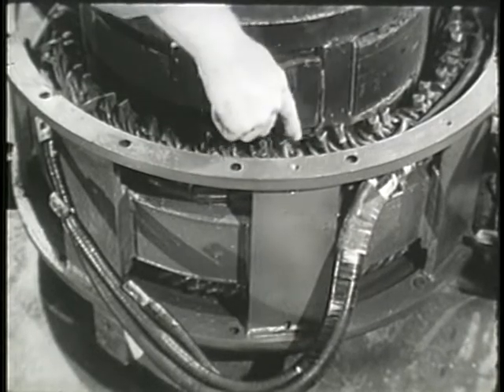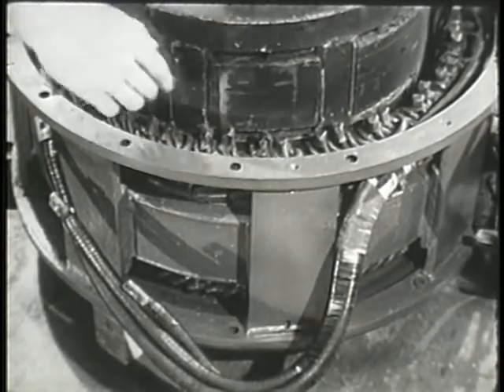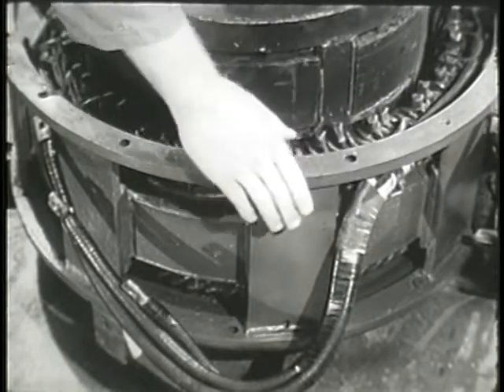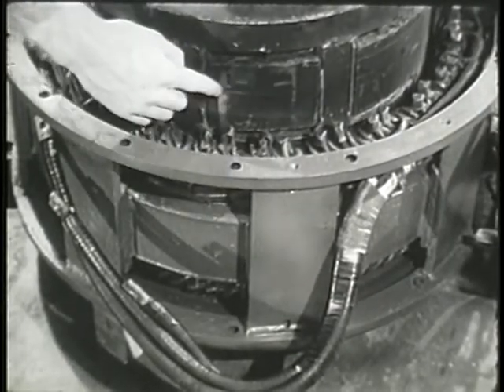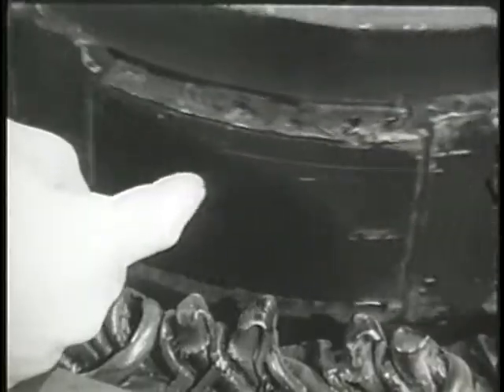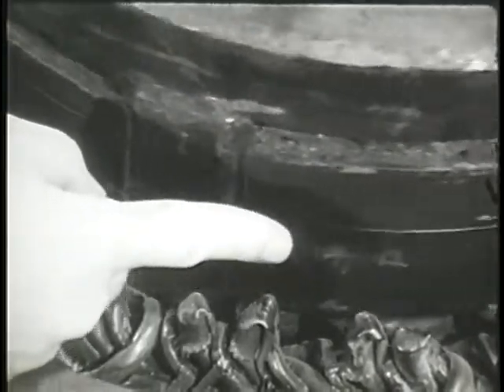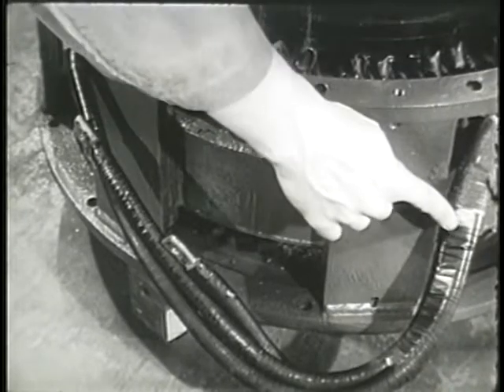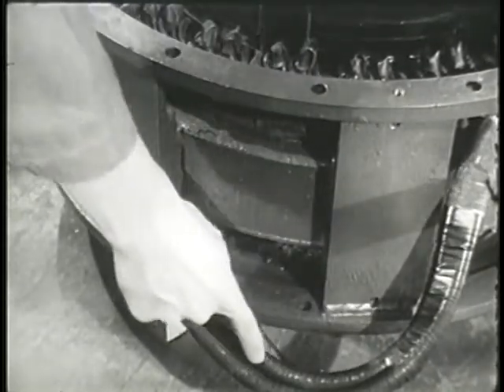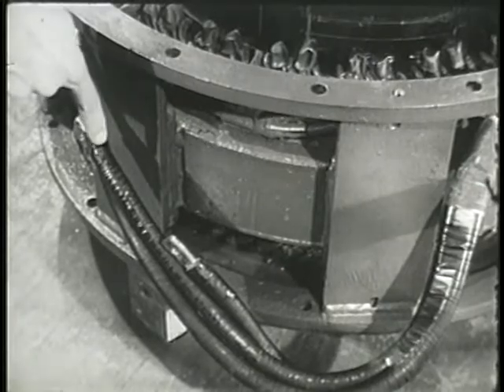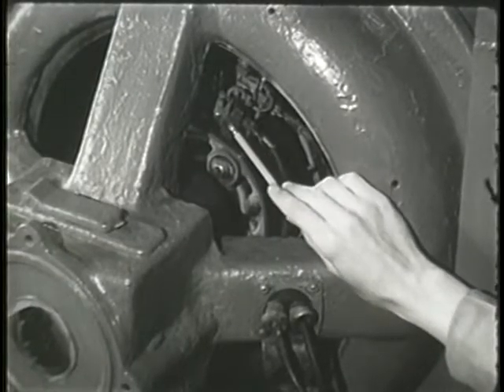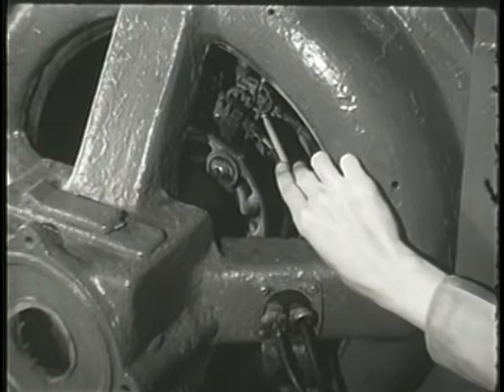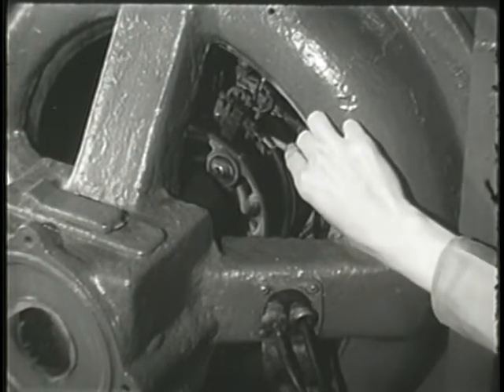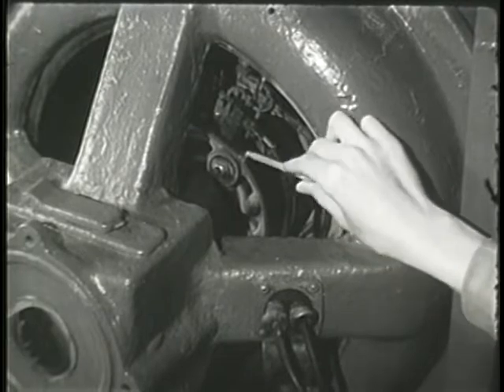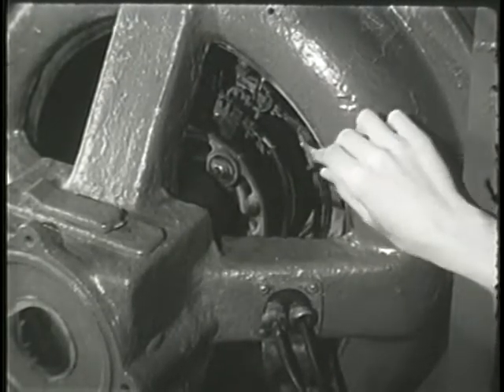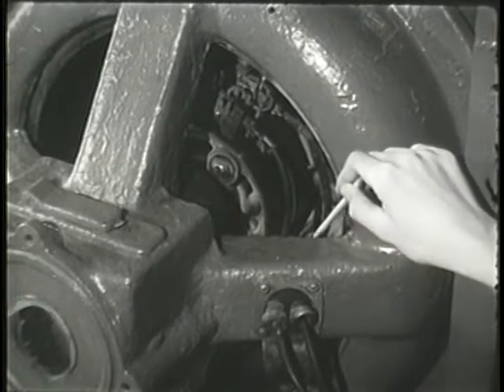Here, the coils of the armature are set around the circumference of the yoke. The poles of the field rotate within the armature to avoid the use of slip rings and to obtain direct connections to the load. Brushes and slip rings are used, however, to connect the AC generator to the outside low voltage DC source needed to excite the field. Sparking brushes at low voltage does not represent a serious problem.